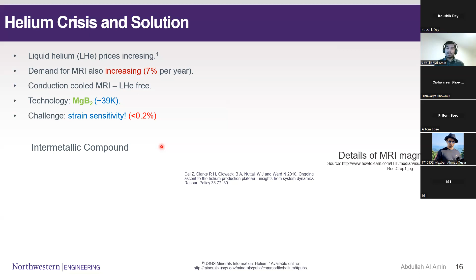When I was doing my PhD, there was a crisis in the price of liquid helium. The prices were going up, and the amount of liquid helium on this Earth is also limited. In MRI, liquid helium is used in a very large quantity, and you cannot manufacture an infinite number of MRI machines because you would run out of liquid helium. So engineers and scientists were looking at different alternatives, and magnesium diboride is one alternative which has a higher critical temperature, meaning it starts to be superconductive at a temperature much higher than other conventional superconductors. Just to give you a reference, magnesium diboride superconducts below 39 Kelvin, whereas the conventional niobium titanium superconducts below 9 Kelvin, which is much smaller.